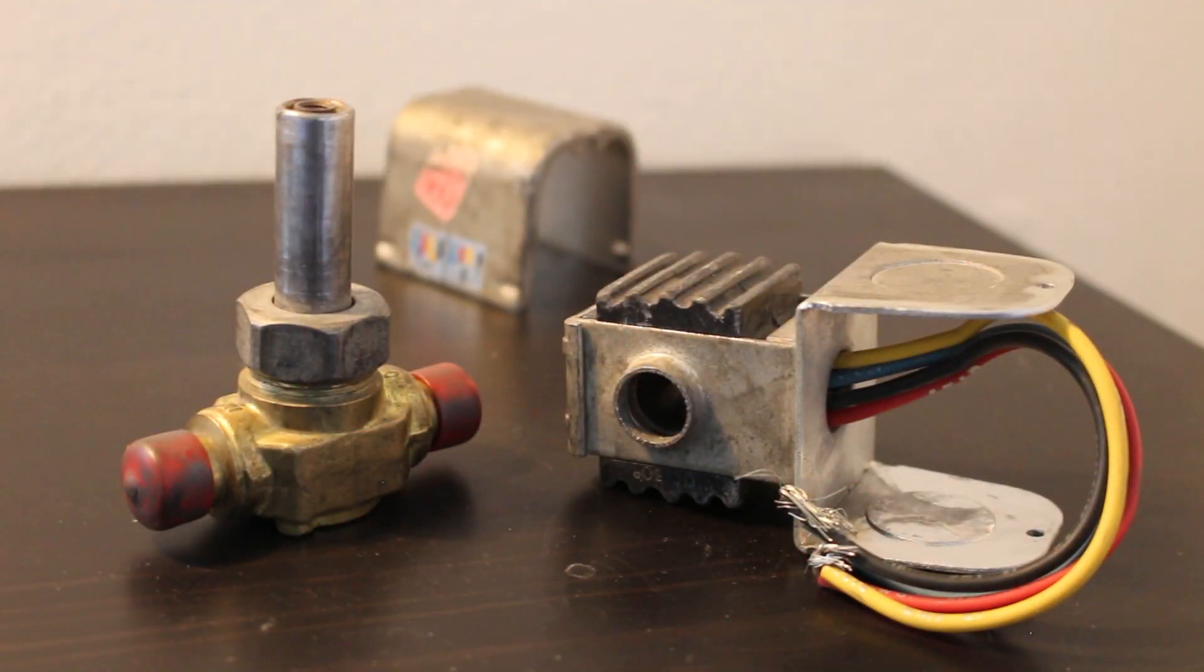The plunger of the solenoid is used to lift the valve off of its seat. The valve is held closed by a spring when it's in its normal or de-energized position, and when the coil is energized, the plunger lifts the valve off its seat and lets liquid or gas flow from the inlet to the outlet.